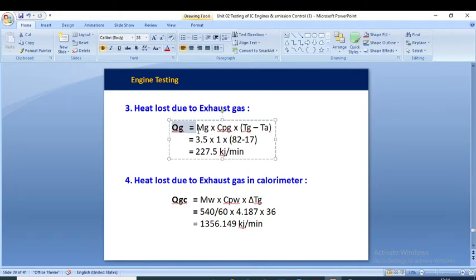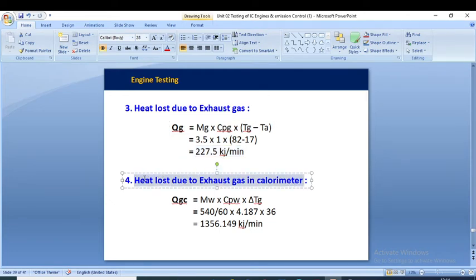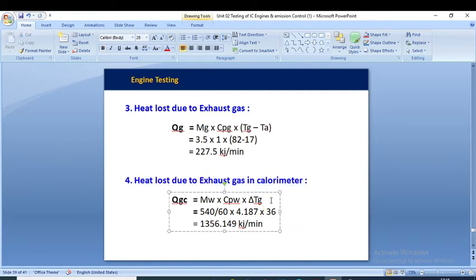Heat loss to the exhaust gas: Q_g = m_g × Cp_g × (T_g − T_a). Putting in the values: 3.5 × 1 × (82 − 17) = 227.5 kJ/min. Since a calorimeter is present, we also calculate heat loss in the calorimeter using Q_gc = m_w × Cp_w × delta T_g. This gives a heat loss in the exhaust gas calorimeter of 1,356.149 kJ/min.